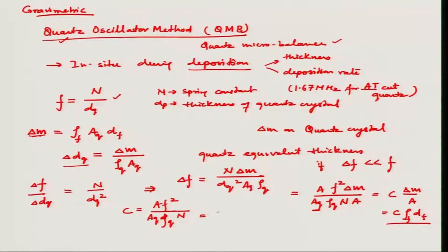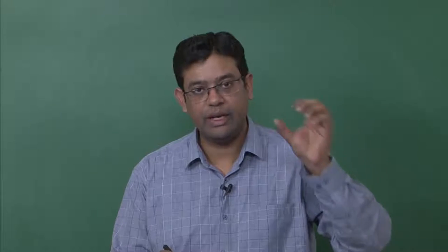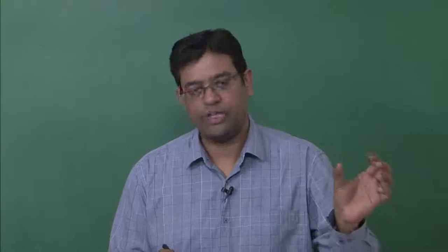This is the weighing sensitivity. So, this is a parameter which can be defined by certain parameters: knowing the natural frequency, the spring constant, the area and the density of the quartz, and relative to the area of the crystal which is exposed for thin film deposition during your deposition process.